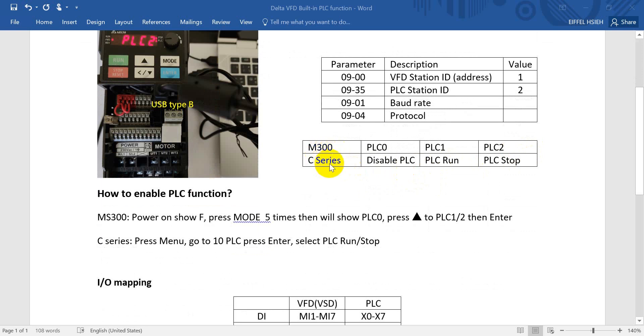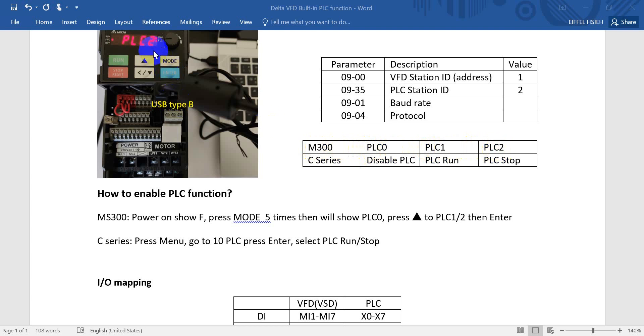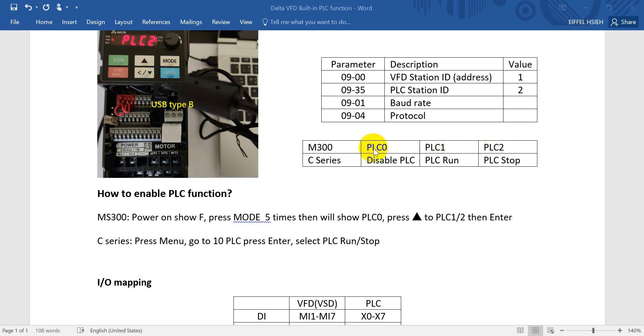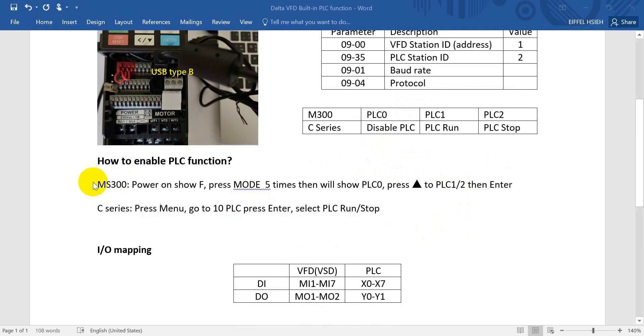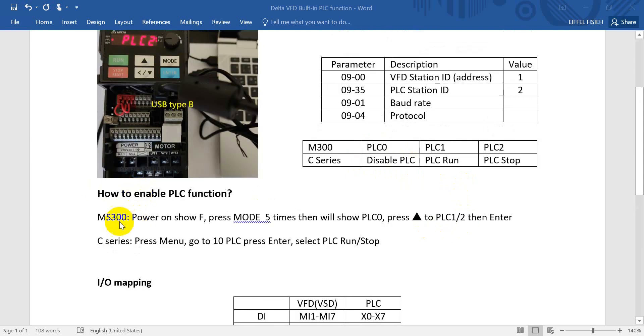And this is one I already mentioned. For M300 series and C series, the name will be slightly different. M300 series will be PLC0, PLC1, and PLC2. So as you can see here, PLC2 means PLC stop, and you can press this one button to decrease the value to PLC1, that means PLC run. And press again you go back to PLC0, so that means we can disable PLC function.